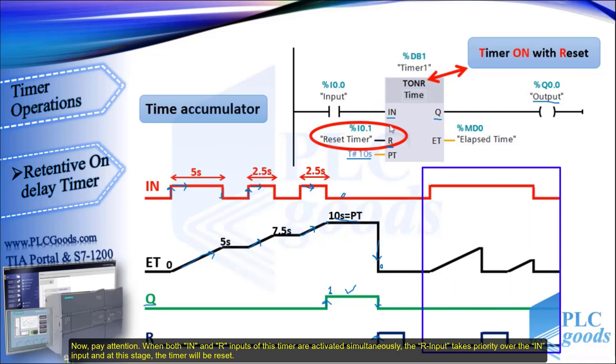Now pay attention when both IN and R inputs of this timer are activated simultaneously. The R input takes priority over the IN input, and at this stage, the timer will be reset.